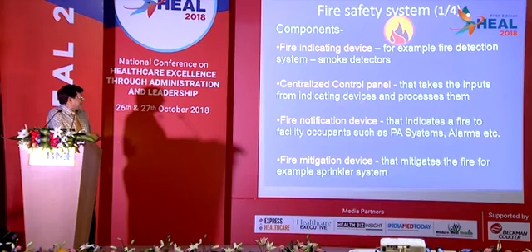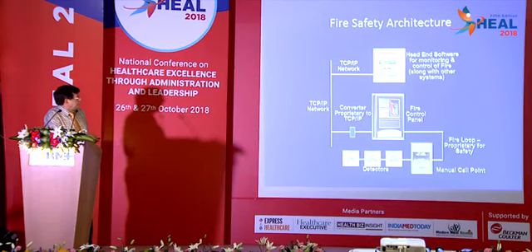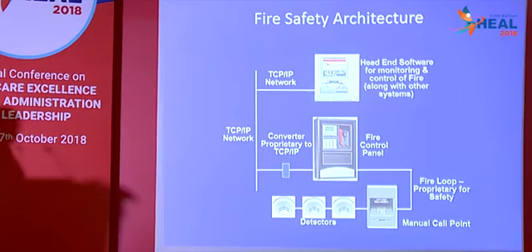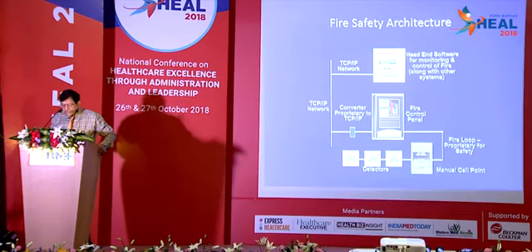Now let us come to the fire safety system. Fire safety will have a fire indicating device, that is a smoke detector. Then we have a centralized control panel that takes the inputs from indicating devices, that is the smoke detectors. Then a fire notification device that indicates a fire to facility occupants, such as a PA system, alarms, etc. And then we have a fire mitigating device, that is the water sprinkler system. Now this is what you will have in your control room. You have a fire control panel and that will be linked to all detectors and the water sprinkler. While sitting in the office, you can see which detector is activated, where the fire alarm is, which fire alarm is activated, and accordingly you can take the action and send the team.